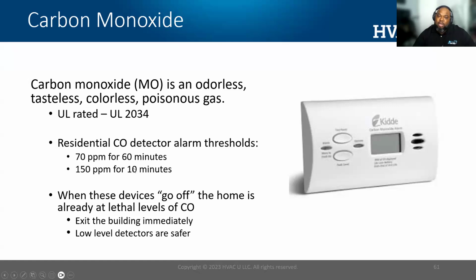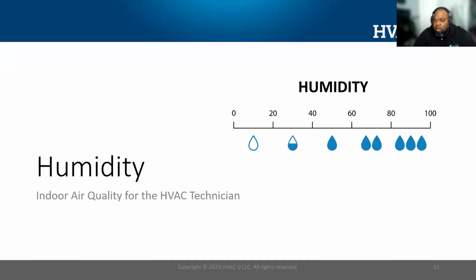Now, when your carbon monoxide detector goes off, it means you are in immediate danger and you should exit the building immediately. All right. However, these will not enunciate at lower levels, and we have established that lower levels can give you flu-like symptoms, and over a sustained period of time, they could be irreversible. So, just something to keep in mind. Maybe supplement your existing carbon monoxide detectors with one that has a digital readout so you can always see exactly what the number is. With that, we'll go into humidity.